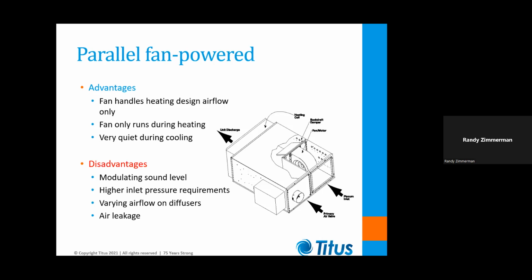And you've also got to deal with varying airflows on your diffusers. So when you're selecting your diffusers, you've got to select them such that they can deal with VAV turn down, which can be problematical for certain types of diffusers. If you're using a high quality, high performance diffuser like a Titus TMS, that's a multi-cone diffuser, or a Titus Omni, that's a plaque diffuser, those can deal with about an 85% turn down very comfortably. Whereas if you've got a low quality, low performance diffuser like a perforated face diffuser, those diffusers with a turn down of less than 15% can actually start to drop their air pattern off the ceiling. Some people refer to that as dumping. I prefer to refer to that as excessive vertical projection because it just sounds a little more scientific.